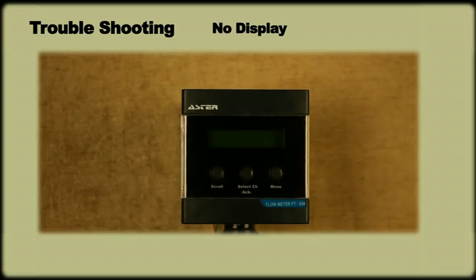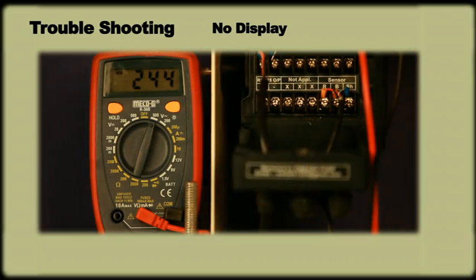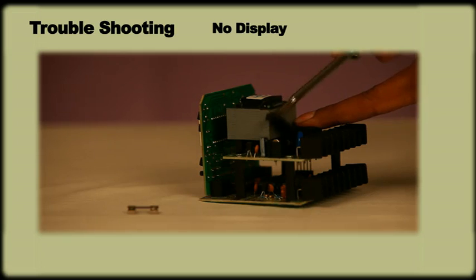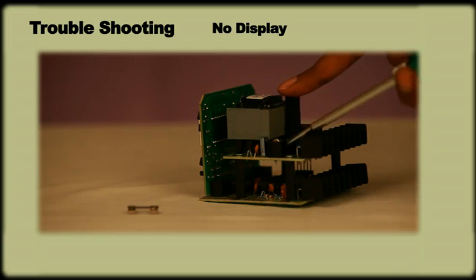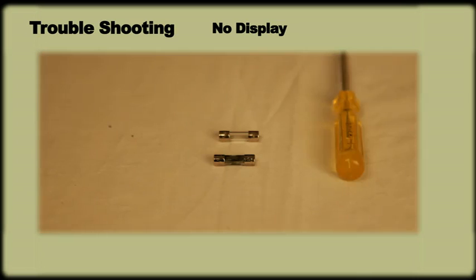Troubleshooting. If the meter shows no display, check the input supply with the help of multimeter and ensure it gets required supply. In case display remains off despite proper input supply, open the instrument and change the fuse with 630 milliampere.